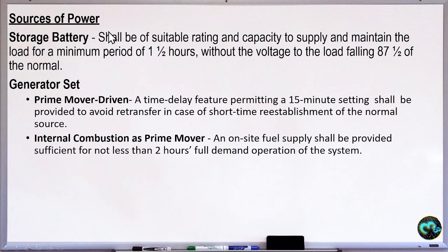Okay, sources of power. If we are using a storage battery, it shall be of suitable rating and capable of supplying and maintaining a load for a minimum of 1.5 hours without the voltage to the load falling below 87.5% of the normal.